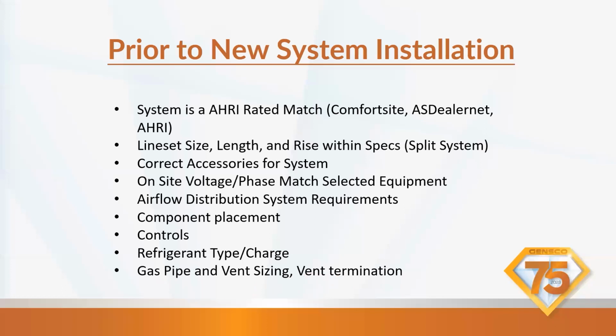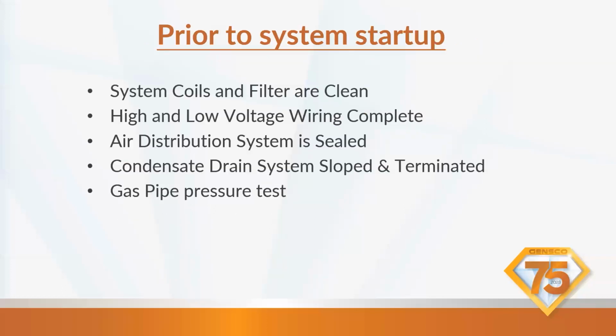Gas pipe and vent sizing, vent termination is critical. We have to make sure our system coils and filters are clean. Again, if we have an ongoing issue with a couple-year-old system, assume that that system coil's dirty and give it a good cleaning, because the only clean coil is the coil you just cleaned. We hear a lot, well, he was just out here 6 months ago to clean the coil. Well, we don't know what he did 6 months ago. So again, the only clean coil is the coil you just cleaned. Filter, number one problem. First thing I always did when I got onto a job site is confirm that I have a clean filter. We want to make sure high and low voltage wiring is complete and secure, nice and tight. Air distribution system is sealed. Condensate drain system sloped and terminated. And then was there a gas pipe pressure test in new construction?